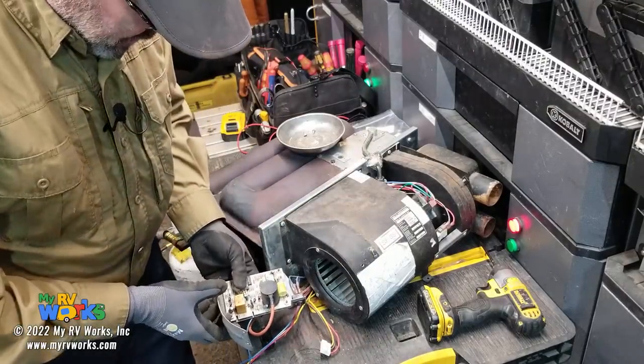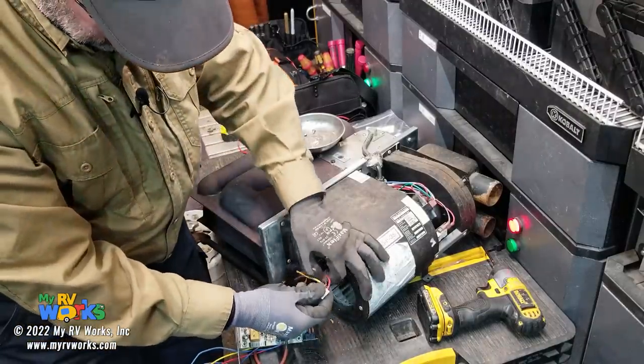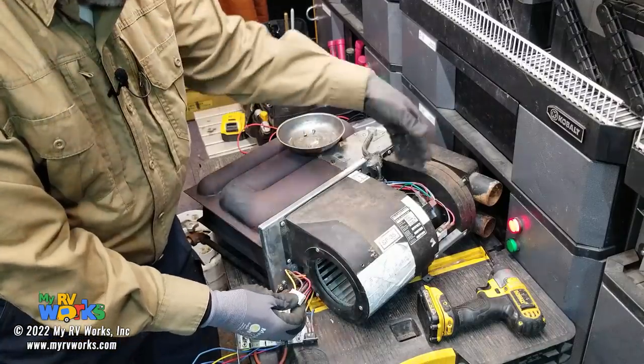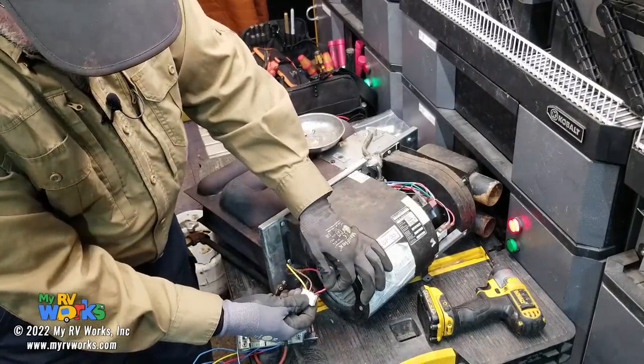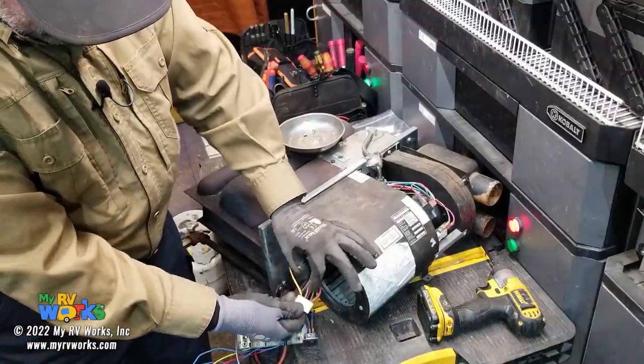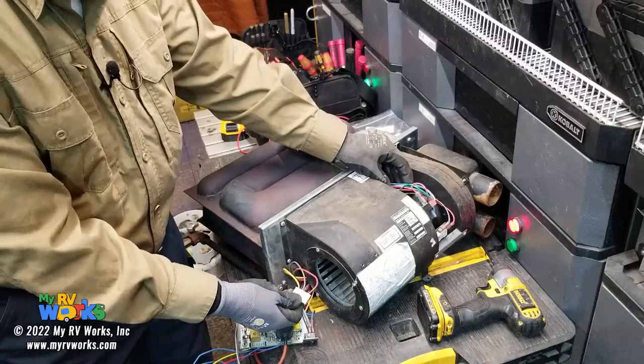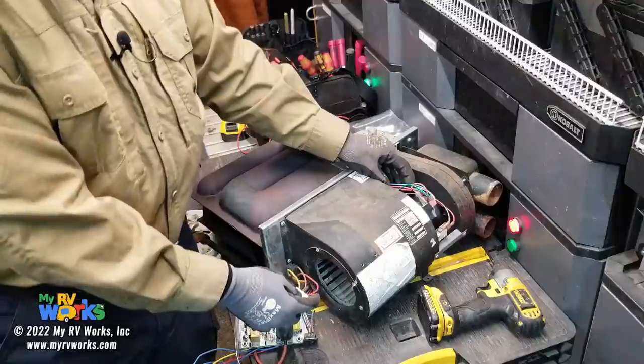Okay. The other thing I'm going to do is on this wire harness, we know that yellow is ground. I'm going to energize my brown wire. Brown wire is going to go to my gas solenoid. So I've got 12 volts coming in on my red wire, telling me that everything's good to go. And then I have 12 volts leaving on the brown wire that's going to open up my dual solenoids. They're redundant solenoids, two of them. They both need to work. If one of them is bad, then it will not work.